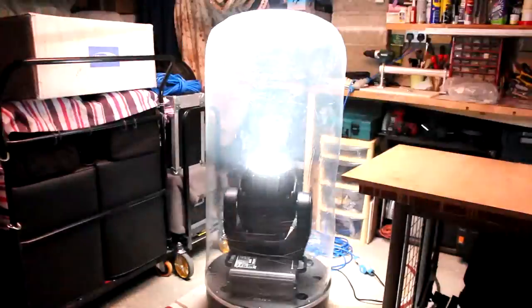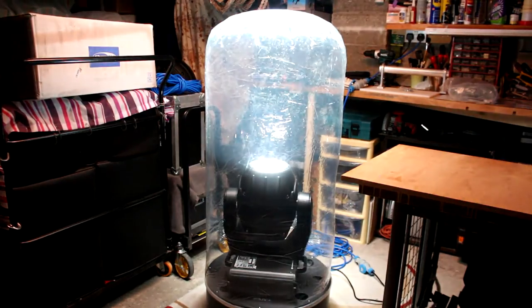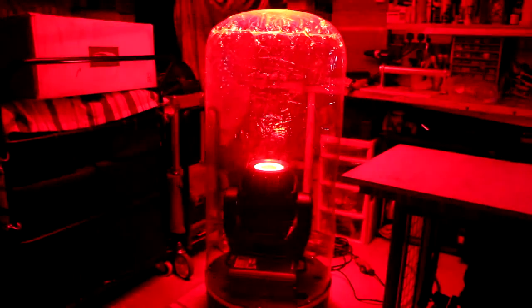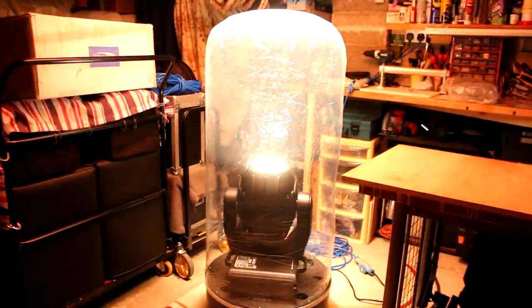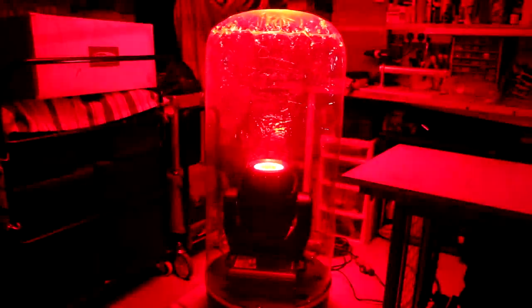What I've done on mine: it comes with a two-pin euro plug on the actual unit itself, but I've switched that out for a 16-amp connector, which you're going to want to do anyway if you're using these outdoors — you don't want anything other than IP-rated connectors. Use arctic blue cable if you're feeding it outdoors, because between the light and the unit itself you're knocking on the door of a thousand watts, so good armored cable is recommended.